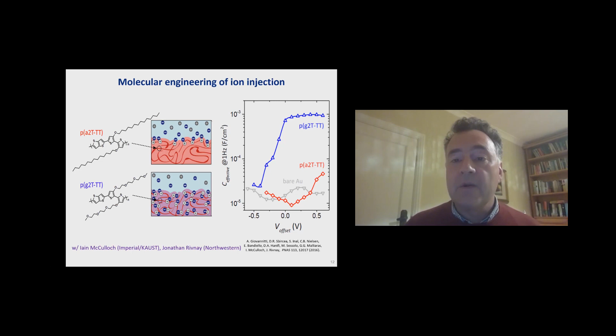In this material, ions will not penetrate in the volume, will stay on the liquid side of the interface, will stay in the brain. And as a result, the coupling between ionics and electronics is very weak and only takes place on the surface of the material. So if you were to measure the so-called capacitance, which describes the strength of the interaction, it would be the same as that of a flat metal film. So a two-dimensional interaction, which is weak. On the other hand, in this material, the addition of oxygen atoms on the side chain allows ions to penetrate into the volume. And then all of a sudden, the capacitance increases quite a lot. So the strength of communication increases.